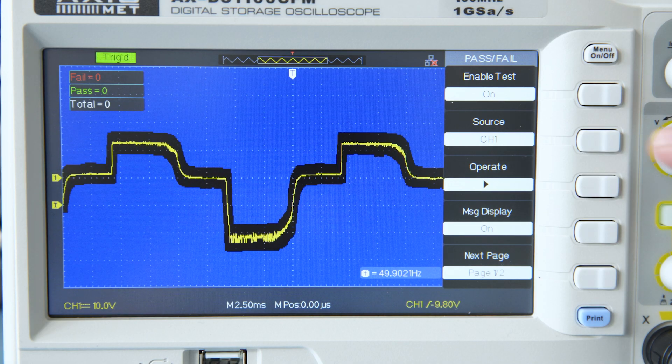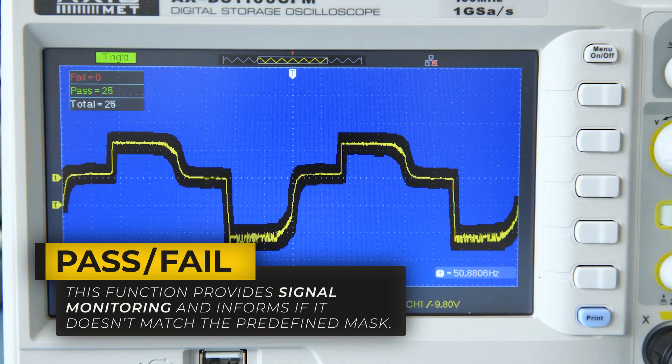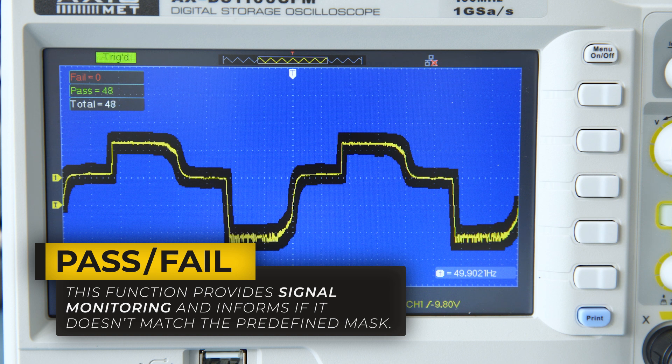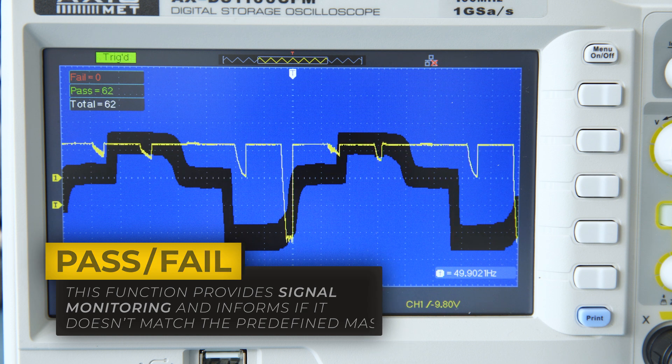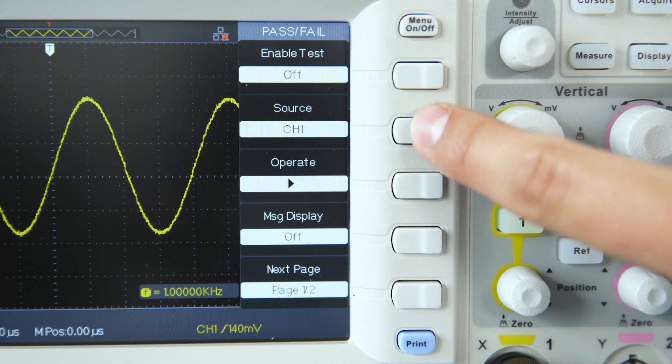Another very useful function of the Oscilloscope is the Pass-Fail test. In this function, the Oscilloscope monitors the signal and outputs a message if the signal does not match the predefined mask.